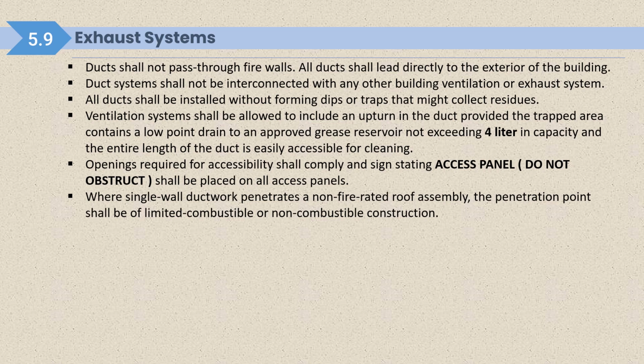Opening required for accessibility shall comply and be marked with a sign stating access panel. So all opening access panels should be marked as an access panel. Do not obstruct shall be placed on all access panels. Where a single wall duct work penetrates a non-fire rated roof assembly, the penetration point shall be of limited combustible or non-combustible construction. So this is talking about the duct.